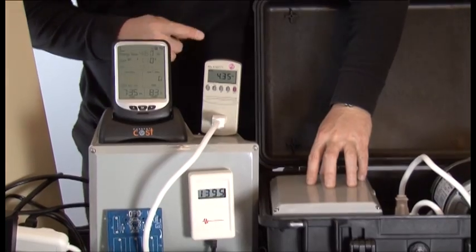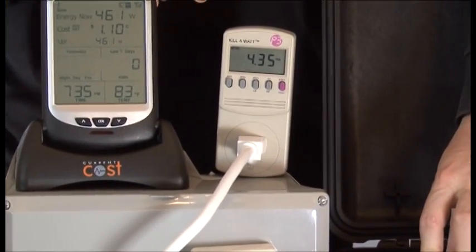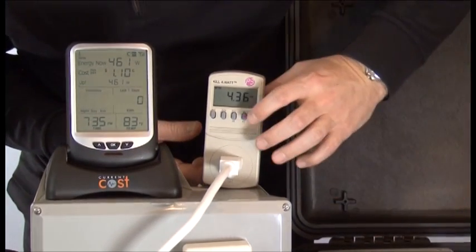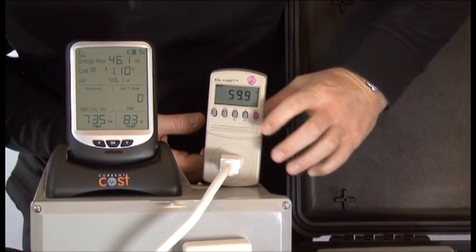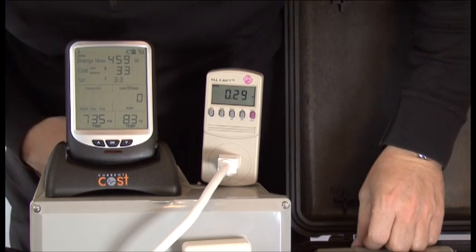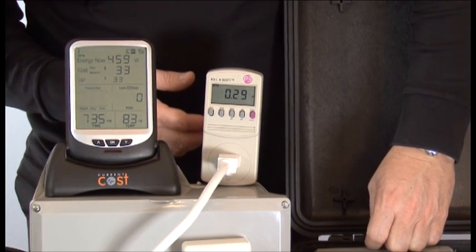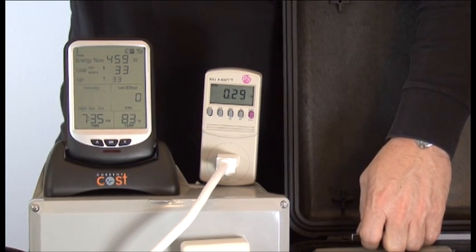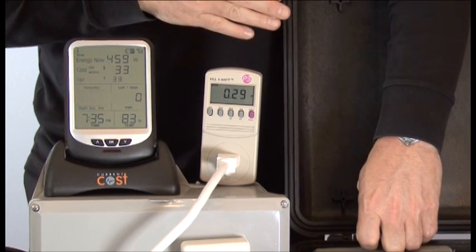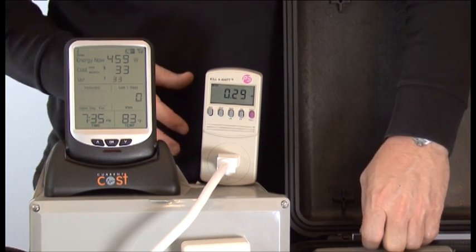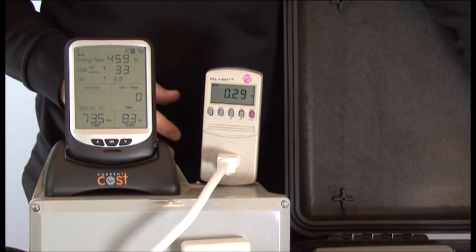Immediately our little amp meter is at 4.5 and our power factor we're going to be at 60 Hertz and our power factor is at 29. Dismal. So only 30% of the electricity we're buying is actually performing work. The extra 70% besides running up our bill is going to cause this little motor to get warm.